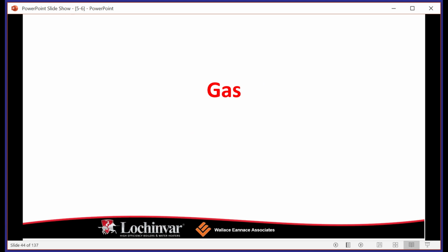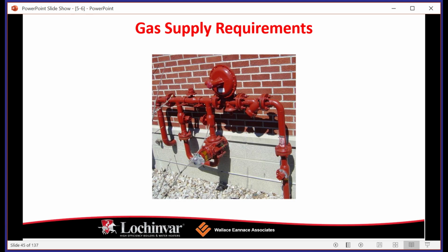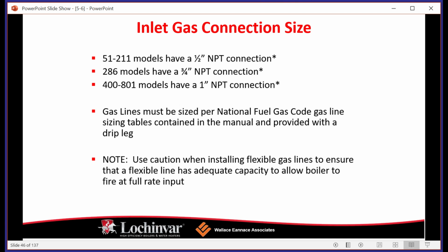Okay, so gas input to the equipment. Gas supply requirements are going to vary by the size of the equipment that you're installing. For example, a smaller light commercial 399,000 BTU input boiler is going to require less fuel than a 6 million BTU input boiler. Gas inlet connection sizes are going to be different based on the size of the equipment. Equipment over 1 million BTUs is typically going to be specified by an engineer, who is also going to be specifying the gas piping manifold sizes if you're putting in more than one boiler. So a lot of this background work is usually done before we get to it.